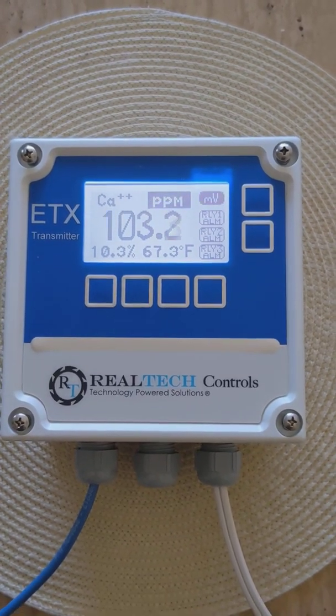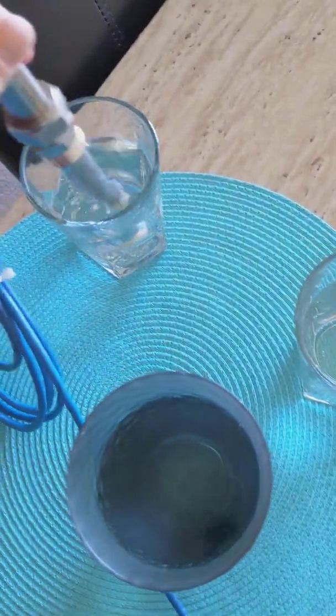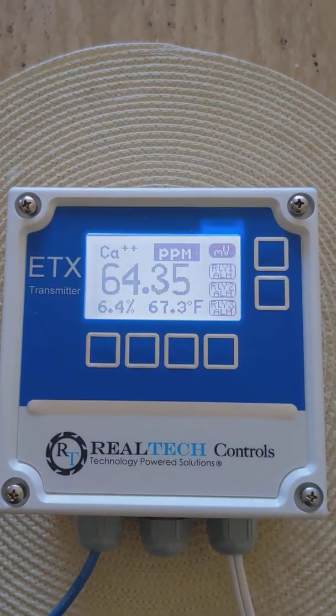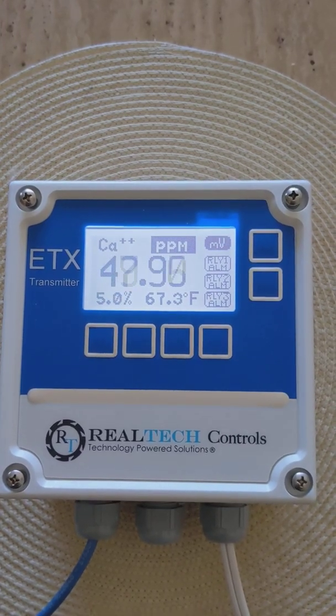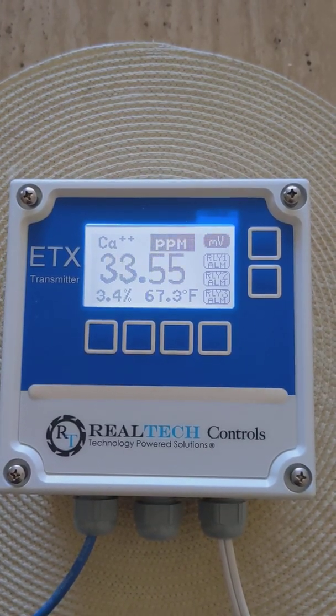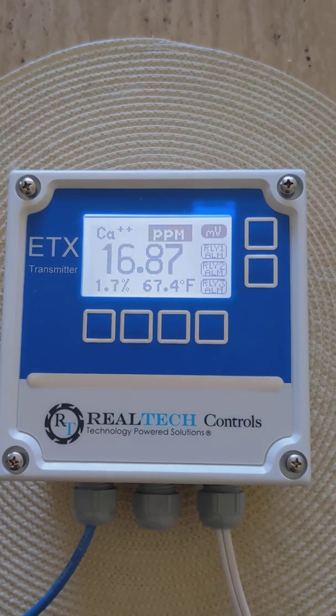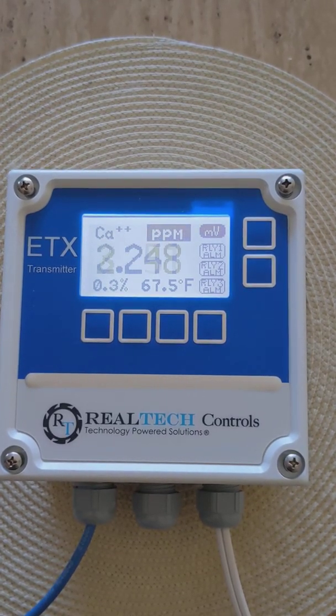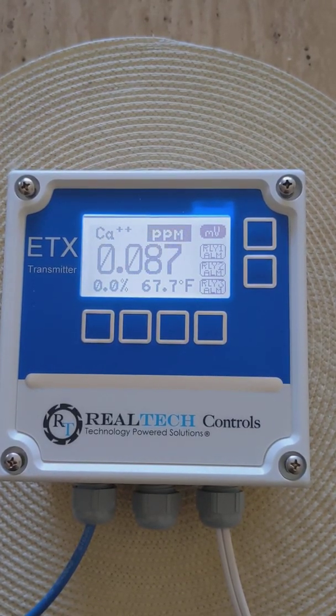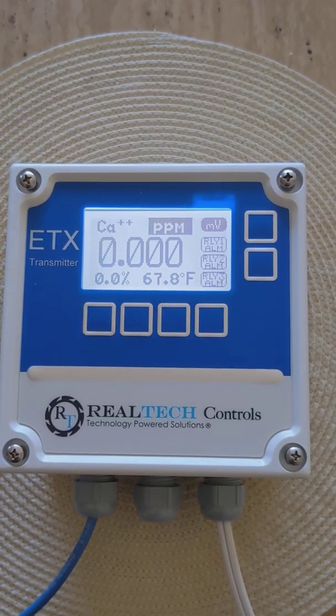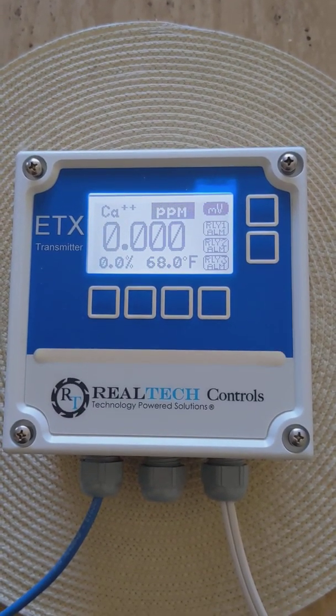Close enough. I'm going to give it a rinse to show you that the 0 value in my distilled or deionized water should be close to 0. And we'll see the repeatability of this unit. Auto ranges the decimal point. There we go, exactly spot on 0.